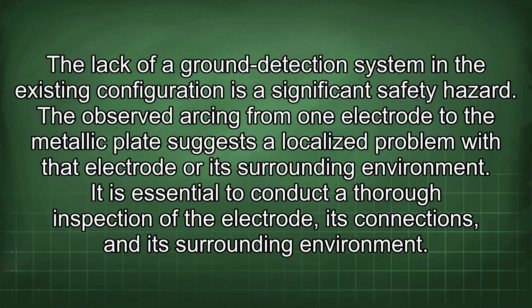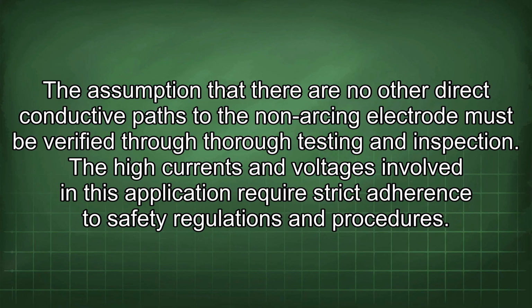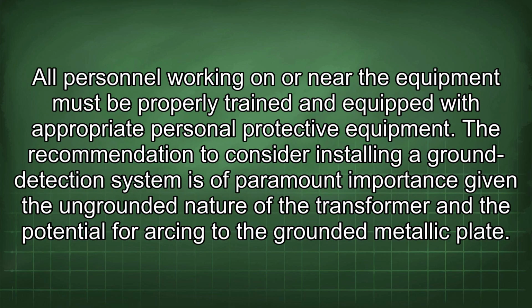The observed arcing from one electrode to the metallic plate suggests a localized problem with that electrode or its surrounding environment. It is essential to conduct a thorough inspection of the electrode, its connections, and its surrounding environment. The assumption that there are no other direct conductive paths to the non-arcing electrode must be verified through thorough testing and inspection. The high currents and voltages involved in this application require strict adherence to safety regulations and procedures. All personnel working on or near the equipment must be properly trained and equipped with appropriate personal protective equipment.